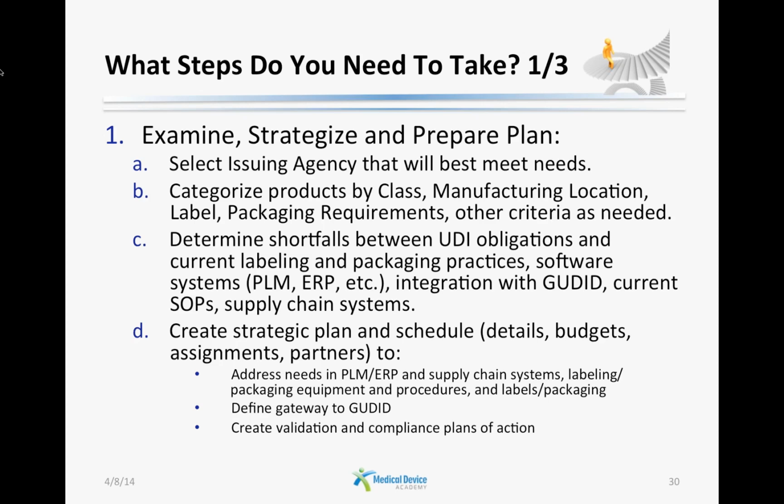In addition to the items on this slide, you will need to determine if 21 CFR Part 11, which pertains to electronic records, revalidation will be required. This is particularly true if you or a third party are using the HL7 SPL process for data submission to GUDID.